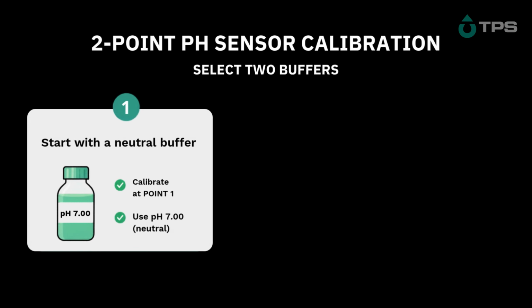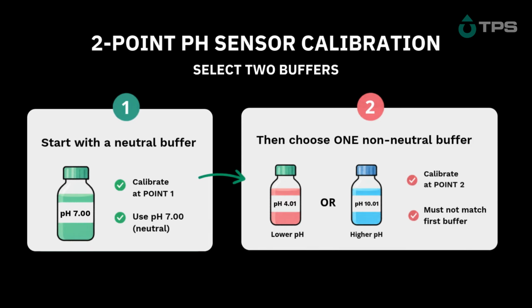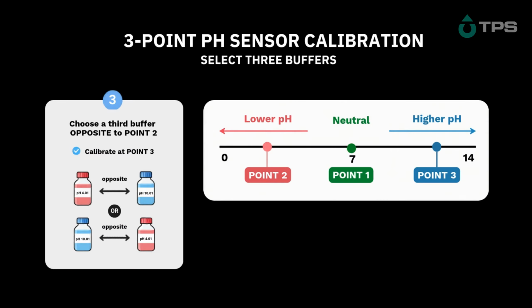If performing a 2-point calibration, you'll need to choose 2 buffers. For point 1, choose a neutral buffer, for example pH 7. For point 2, choose a different buffer from the same set. In this video, we're using the USA buffer set, using pH 7 for point 1 and pH 4 for point 2. For a 3-point calibration, also select a third buffer that is opposite on the pH scale to your secondary buffer. We'll be using pH 10 for our third point.